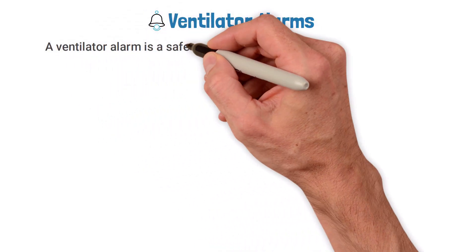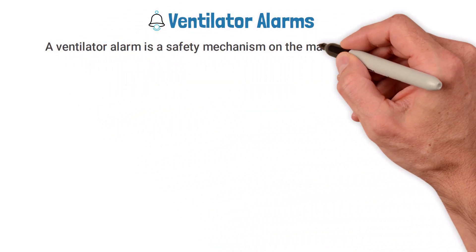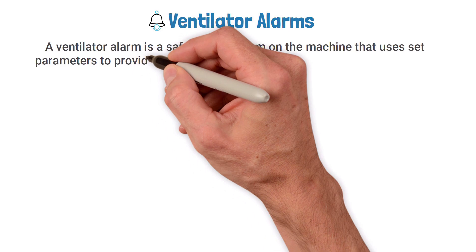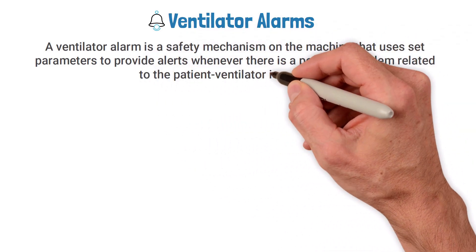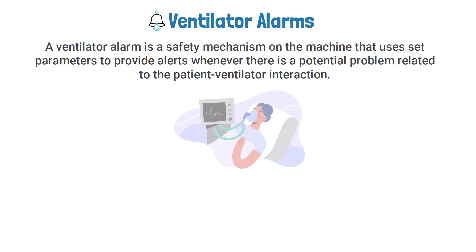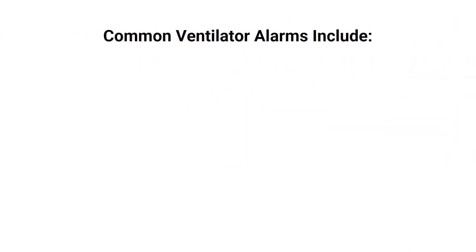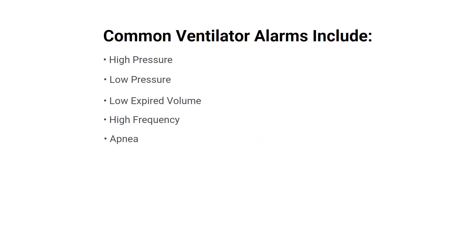The last setting we need to discuss is the ventilator alarms. A ventilator alarm is a safety mechanism on the machine that uses set parameters to provide alerts whenever there is a potential problem related to the patient-ventilator interaction. Some of the common ventilator alarms include high pressure, low pressure, low expired volume, high frequency, apnea, high PEEP, and low PEEP.